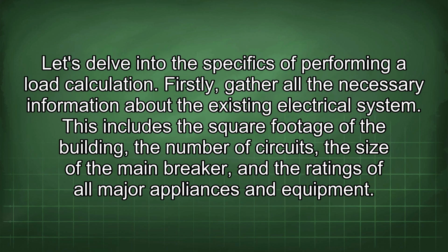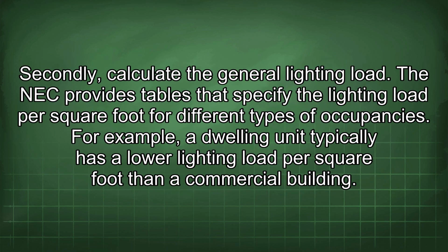Let's delve into the specifics of performing a load calculation. Firstly, gather all the necessary information about the existing electrical system. This includes the square footage of the building, the number of circuits, the size of the main breaker, and the ratings of all major appliances and equipment. Secondly, calculate the general lighting load. The NEC provides tables that specify the lighting load per square foot for different types of occupancies.